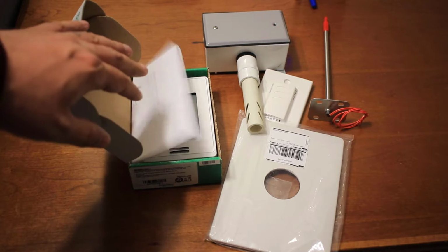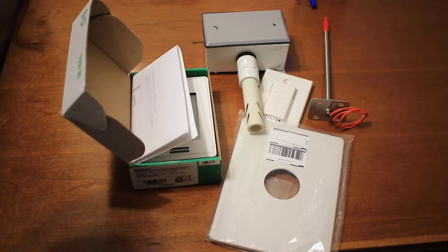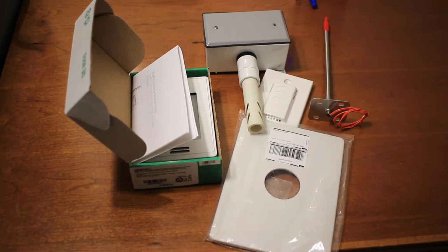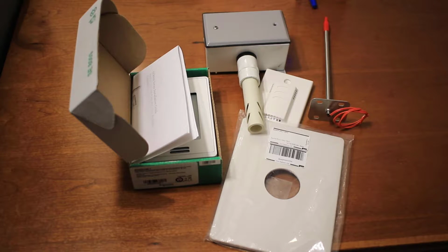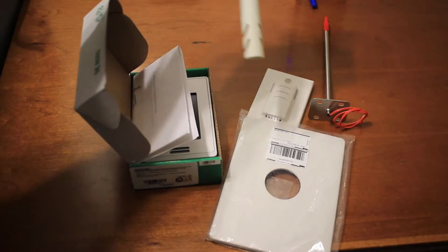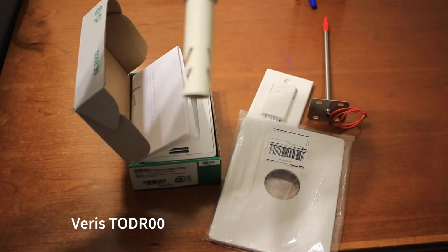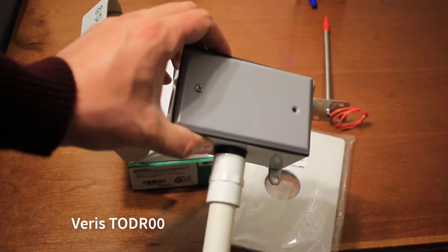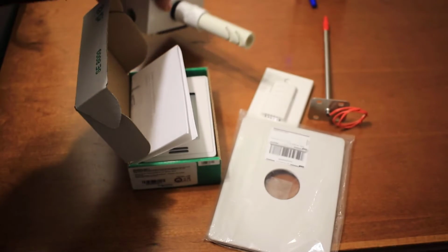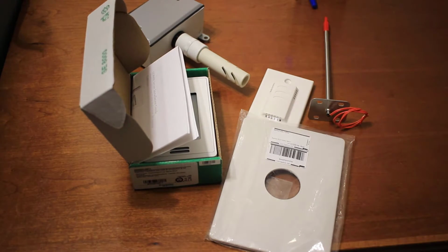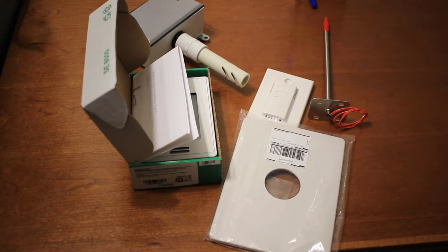Now, going around in a clockwise fashion, the first device you're going to see up here is our outdoor temperature sensor. If we want to be getting readings locally as to what is the outdoor temperature, we can connect this up. It again comes in a wonderful weather-tight box. You just place that out, wire that up to our SE8000 directly. When you wire it up to the first SE8000, it will automatically bring in your temperature and push that across to all of your other SE8000s. So you only need one of these out on a site.